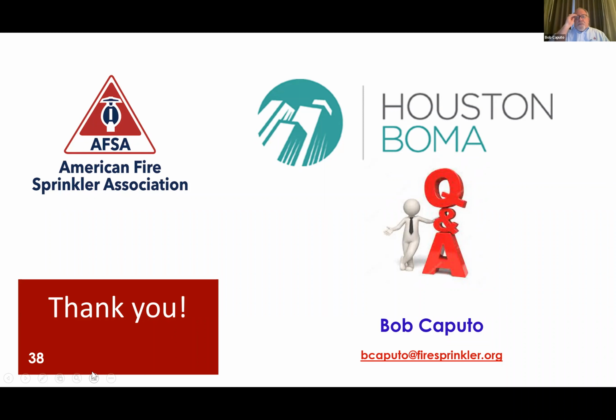So I'm assuming, because BOMA stands for Building Owners and Managers Association, that most of you are managing buildings as opposed to being leasing agents. And I wasn't really sure what your interest level was in the knowledge, not just of storage occupancies. I do want to note that fire pumps, if you have a fire pump, and a lot of storage buildings do, especially in Houston. Houston's a little unique in that it requires a break tank. So when the water comes into the building, there's going to be a big square water storage tank. And that fire pump is going to suck the water out of that tank while the municipal water supply fills that tank. There's also something called a backflow preventer.